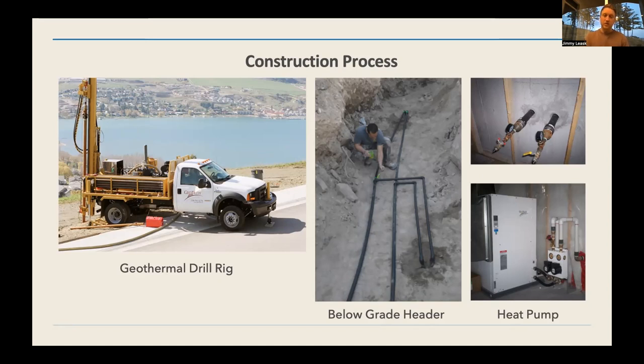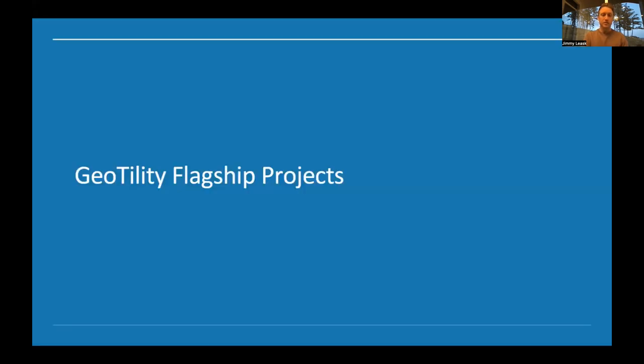As you can see, we have one of our guys tying in that below-grade header, which then gets stubbed into the mechanical room over here. From there it connects to a flow center that marries up between the heat pump and the ground loop, and that flow center circulates the fluid between the fields.